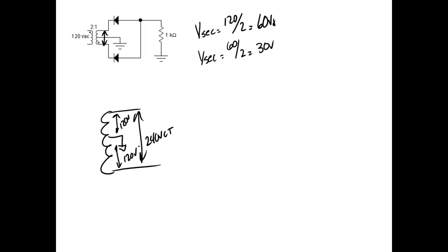So we've got an option of two voltages — a higher voltage available off the center-tap transformer and then a lower voltage. You need to stagger these — if you notice the circuit breaker panel, it's got two sides. These 120-volt circuits, you're supposed to stagger them on each side. If you've got five on this side, you should have five on that side, because if you don't, you're going to be loading one side of the transformer down. So try to stagger those — sometimes it doesn't work out perfectly.